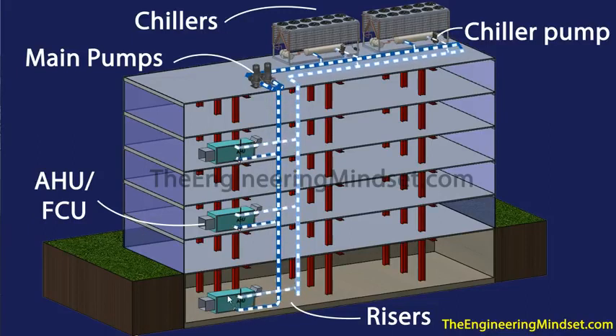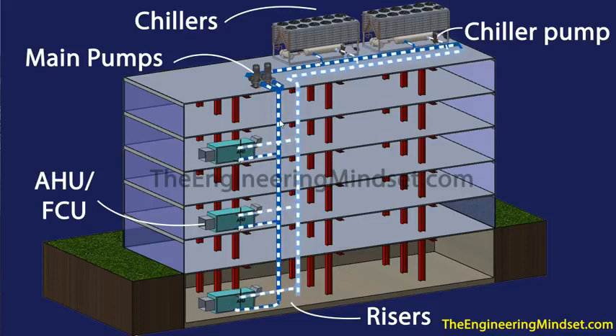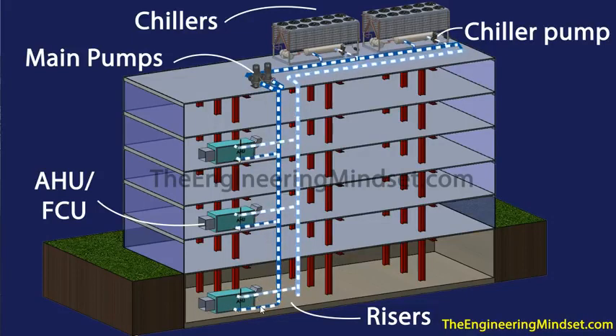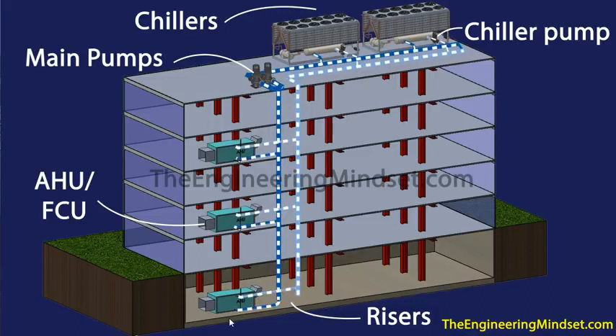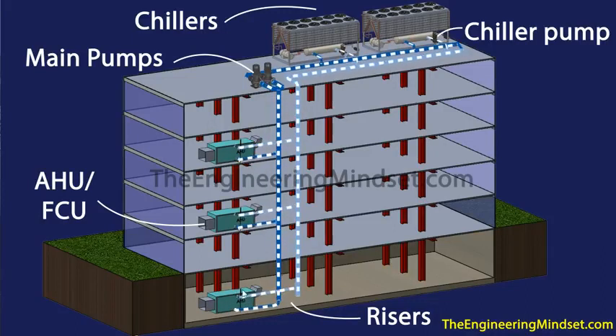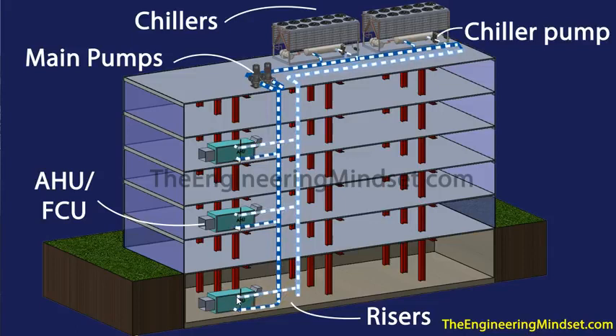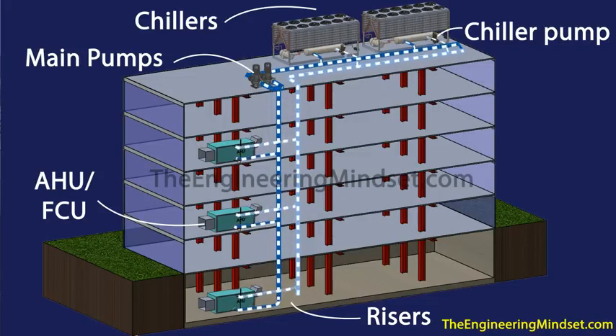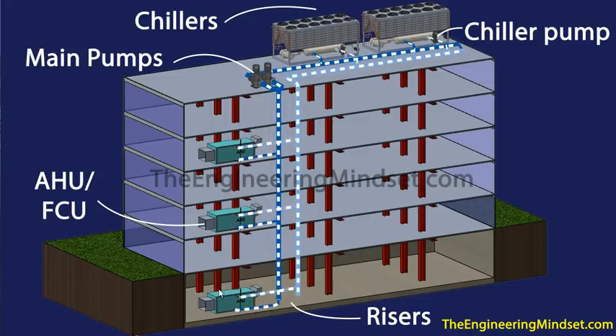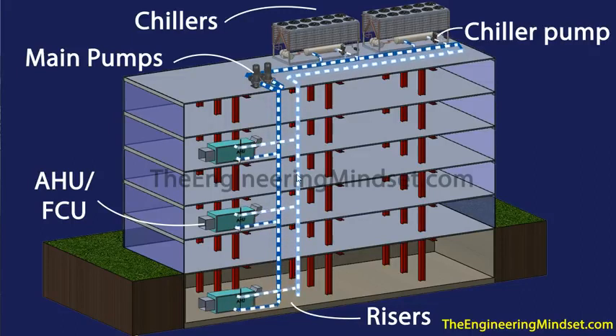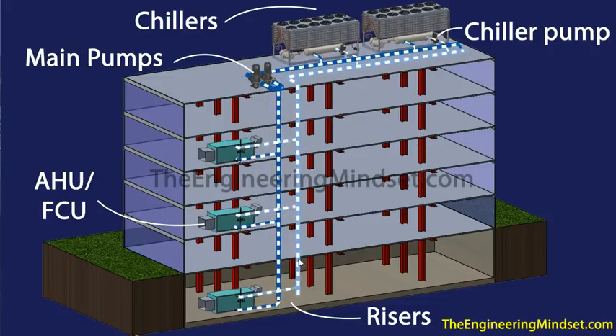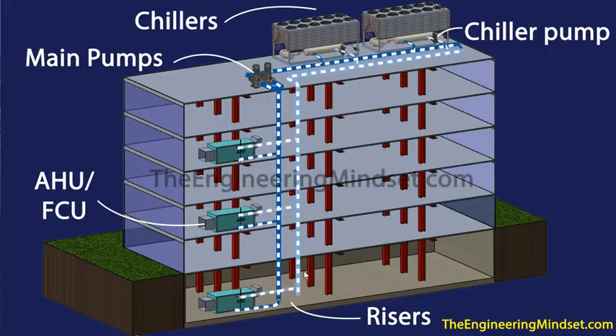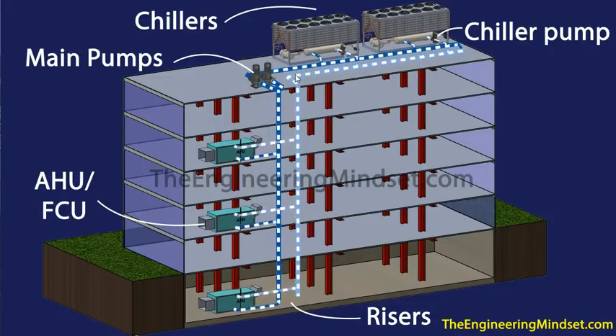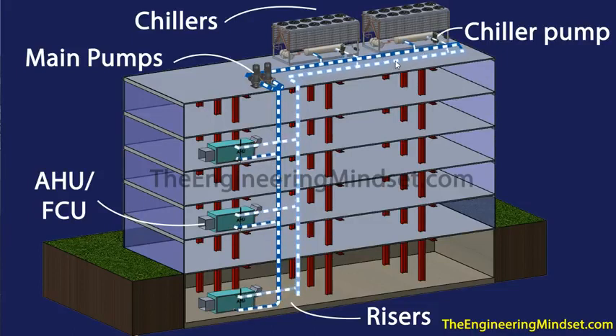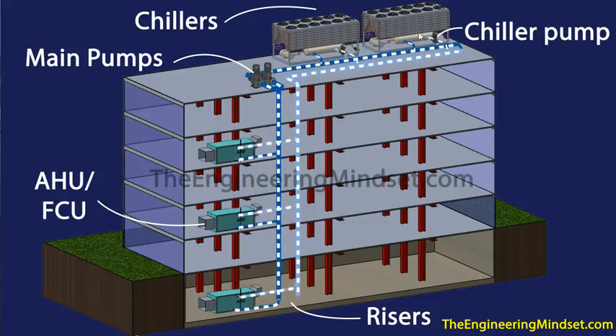Once that has been used, it will then return. It will probably go in at around 6 degrees Celsius, which is about 43 degrees Fahrenheit, and it will then leave here back into the return at about 12 degrees Celsius or 54 degrees Fahrenheit. Now, all of this will then add up into these, which are known as risers, and that water, it's still called chilled water even though it's now warmer, will then return. So this is return chilled water, and that will make its way back up to the top here, where it will then enter off into the chillers and repeat that cycle.